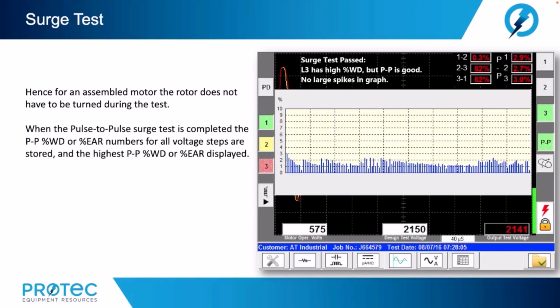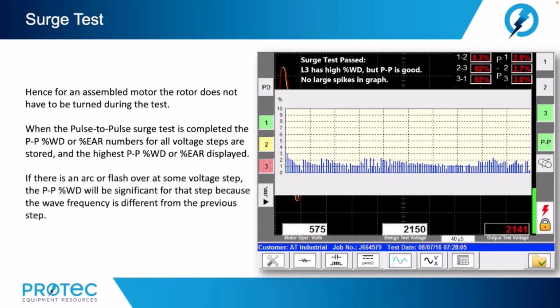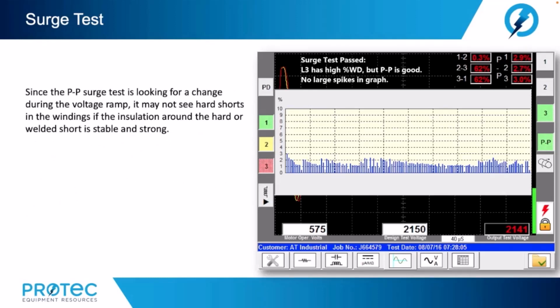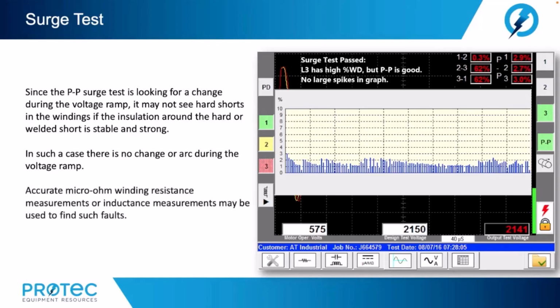When the pulse-to-pulse surge test is completed, the P2P %WD or %EAR numbers for all the voltage steps are stored, and the highest P2P %WD or %EAR are displayed. If there is an arc or flashover at some voltage step, the P2P %WD will be significant for that step because the wave frequency is different from the previous step. Since the P2P surge test is looking for a change during the voltage ramp, it may not see hard shorts in the windings if the insulation around the hard or welded short is stable and strong. In such cases, there is no change or arc during the voltage ramp. Accurate micro-ohm winding resistance measurements or inductance measurements may be used to find such faults.